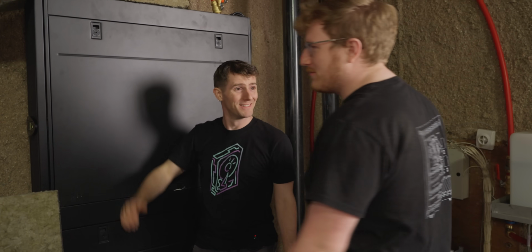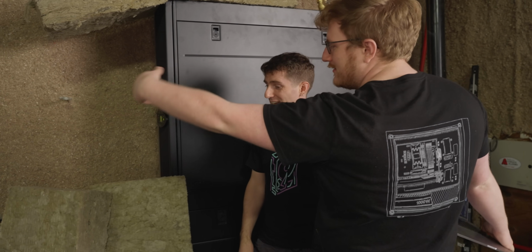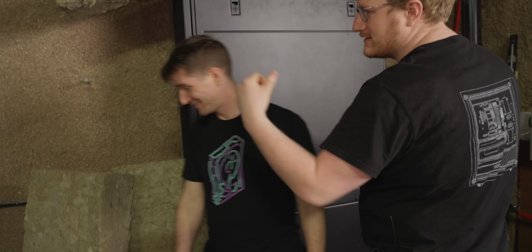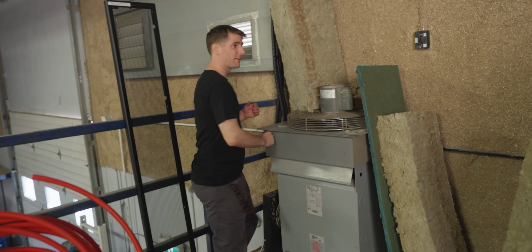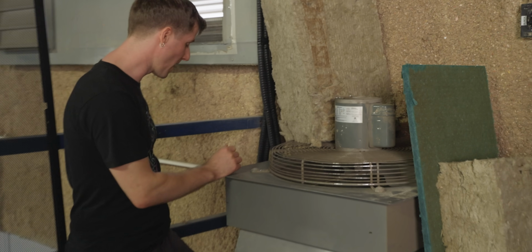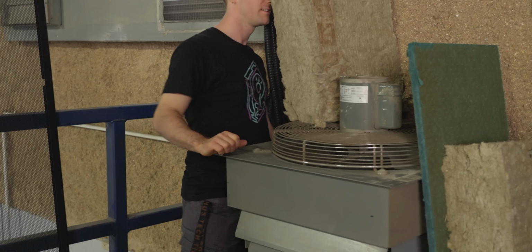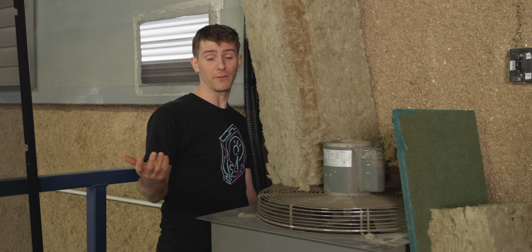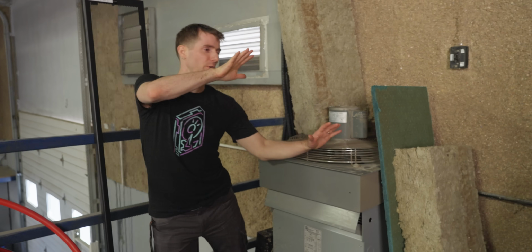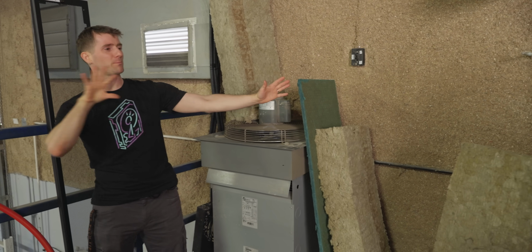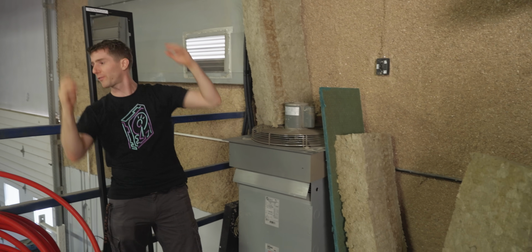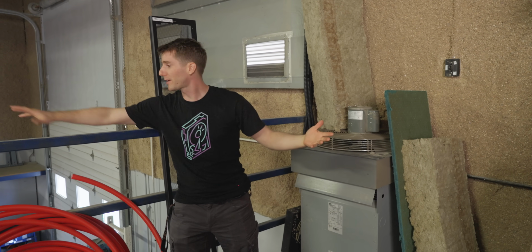Long term, we get a sheet of plywood and attach the rock wool on the inside of it to kind of make a baffle. If I stand here, it's pretty loud, but if I go behind this thing, it's a pretty substantial difference. We just have to create kind of a sound-blocking maze that air can move through, but blocks sound from reaching people below us. And it's also at like 80% fan right now. If we put a second one up here and run them at half the speed, it should be tolerable.